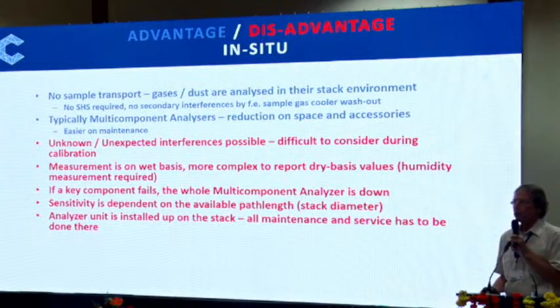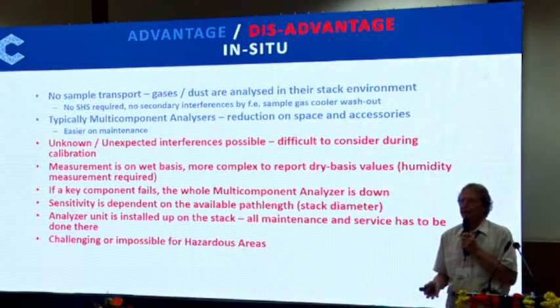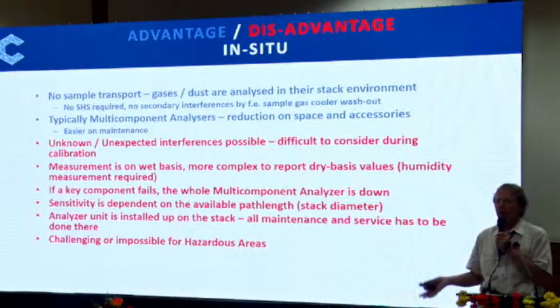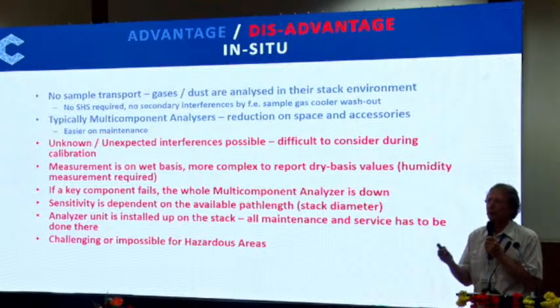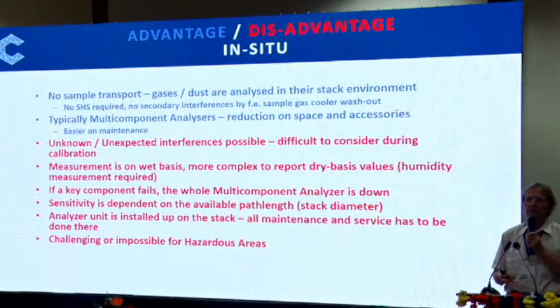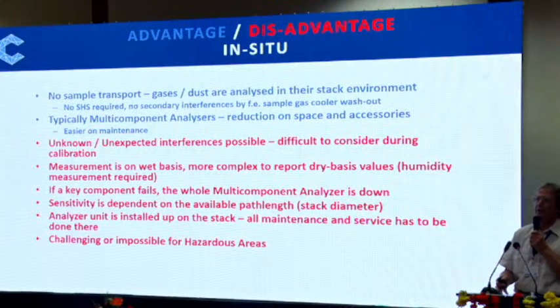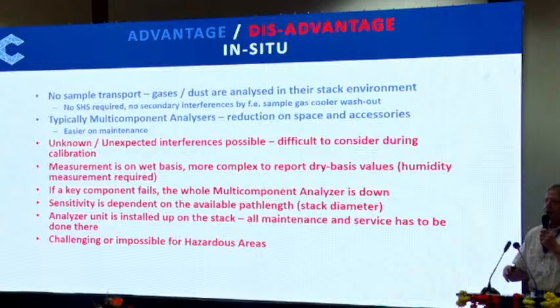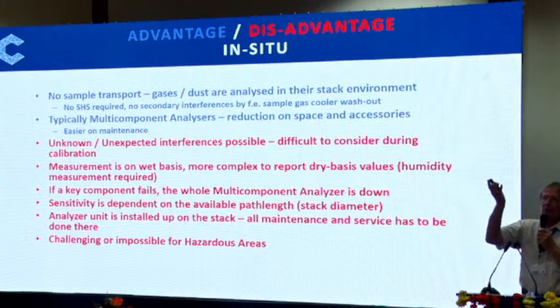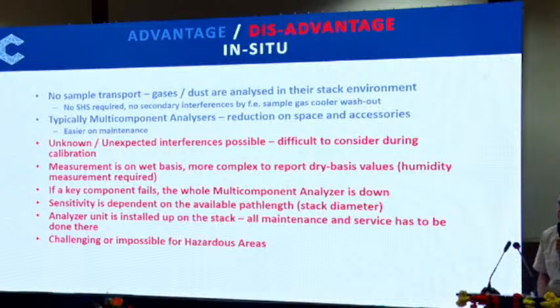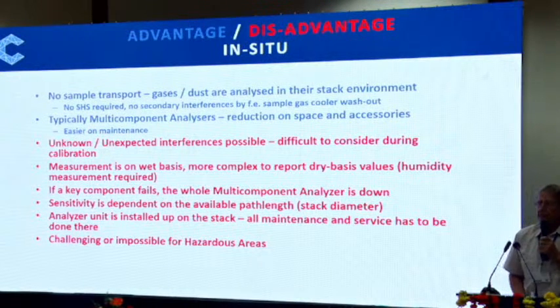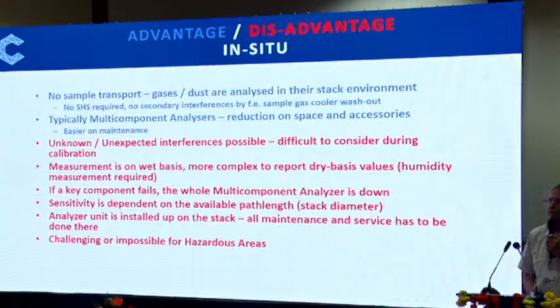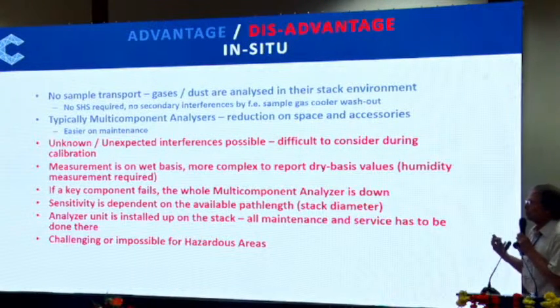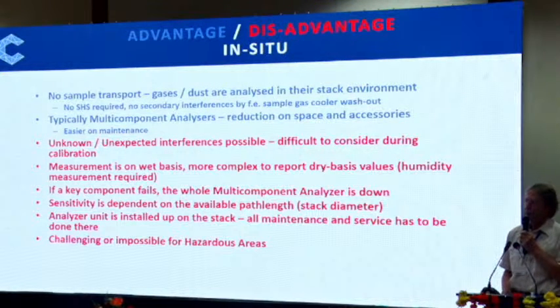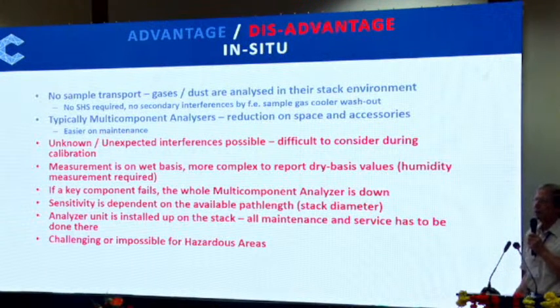Very important, my reporting is required on dry basis. An in situ analyzer, like a dust monitor, or like gas analyzers, they work on wet basis. So I have to correct them for moisture content, because the moisture in the stack is a diluting factor. After I take out the moisture of the stack, calculate it out, my concentration goes up automatically. Sensitivity, path length, stack diameter, very important point, because my path length goes into the sensitivity of my system. And the longer my path length is, the lower is my lowest detectable concentration.